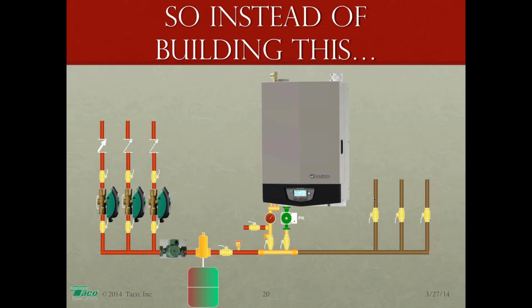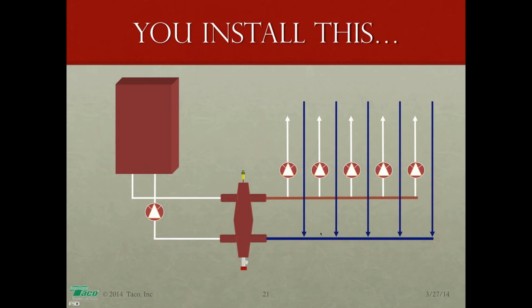You could build this with your oversized header and build this whole thing right here, this whole setup right here, all right? You could build that in the field and size it appropriately, size it as needed. Or you could install this, meaning you could buy that thing, bang it on the wall, hook up your boiler, hook up your distribution, and call it a day. Your call. If you oversize the header, they're going to do essentially the same thing. One, you bang on the wall and it's done for you. Another, you have to make yourself. Okay? But ultimately, sized properly, they'll both do about the same thing.